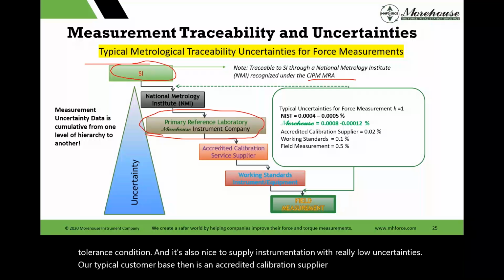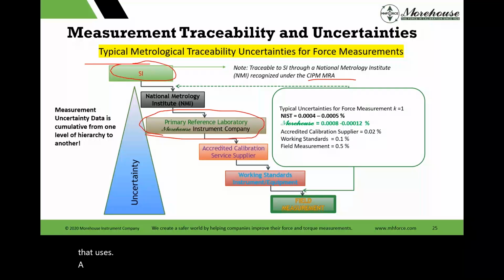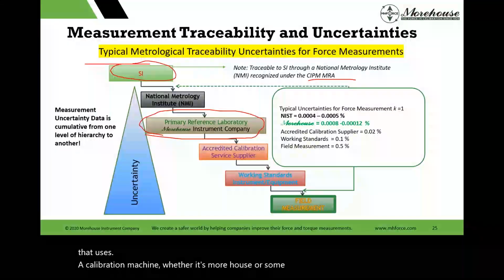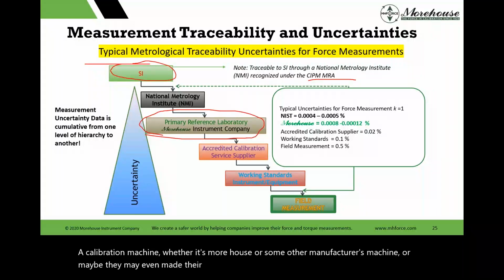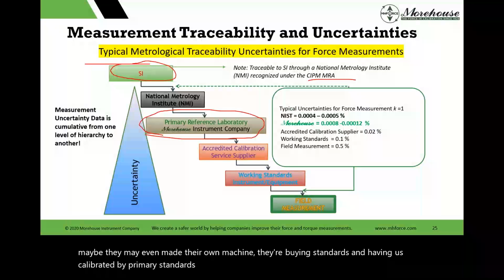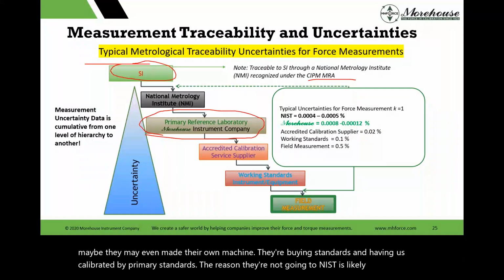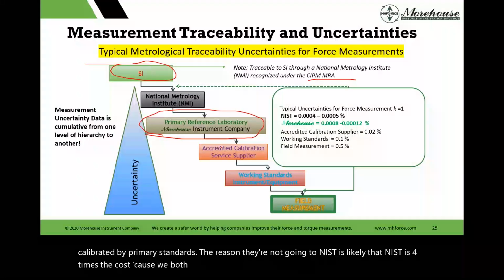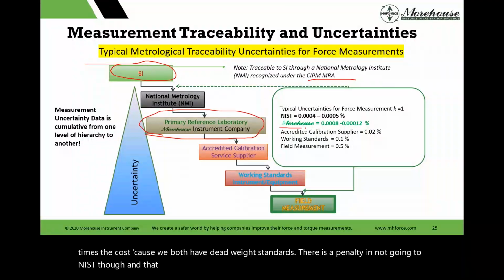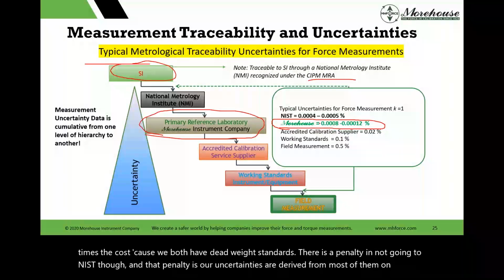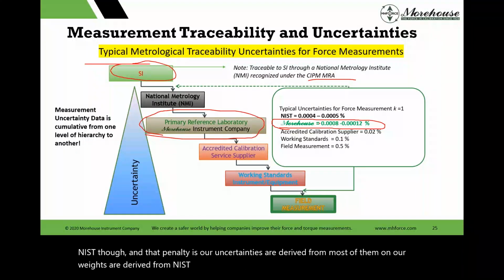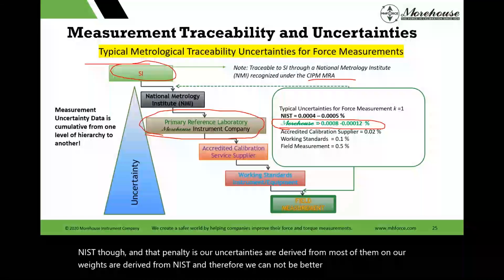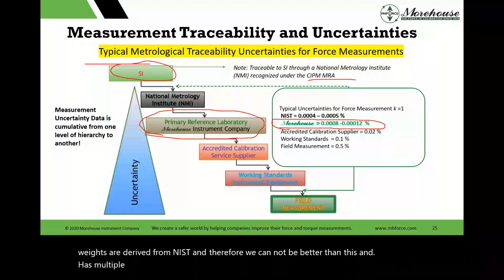This would be someone that uses a calibration machine, whether it's Morehouse or some other manufacturer's machine, or maybe they even made their own machine. They're buying standards and having us calibrate them with primary standards. The reason they're not going to NIST is likely that NIST is 4 times the cost, because we both have deadweight standards. There is a penalty in not going to NIST though, and that penalty is our uncertainties, most of them on our weights, are derived from NIST, and therefore we cannot be better than NIST, and NIST does multiple measurements and really beats their numbers down.